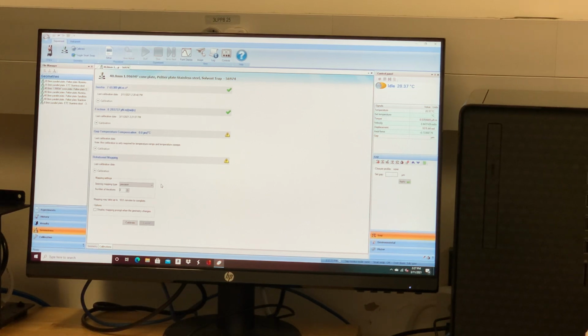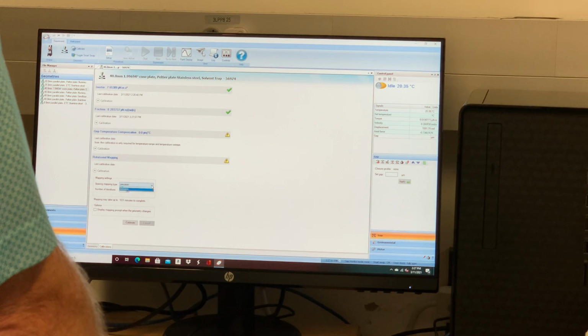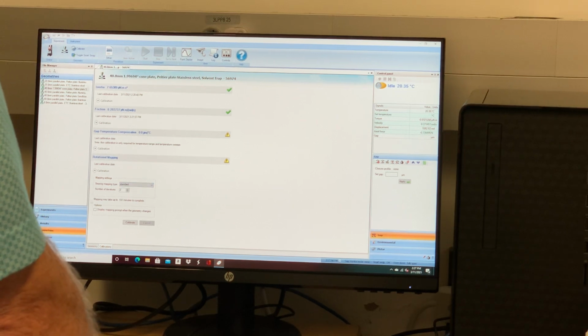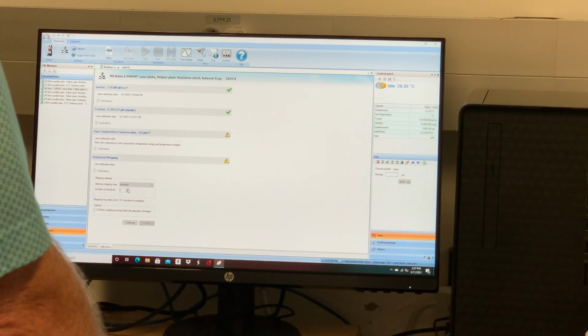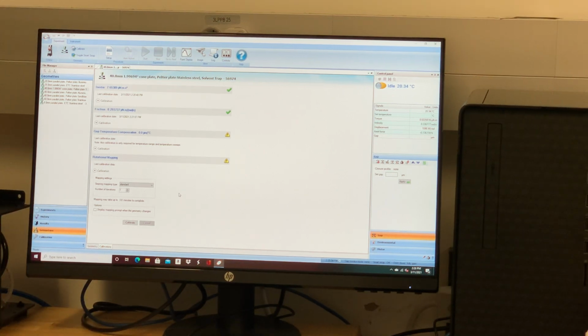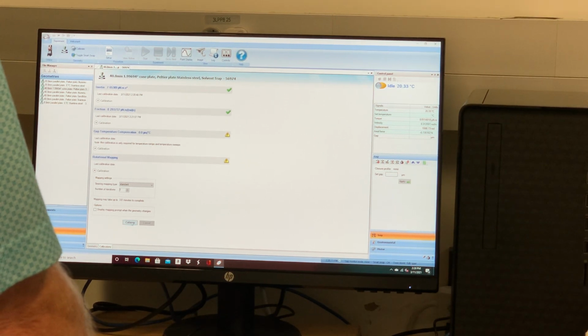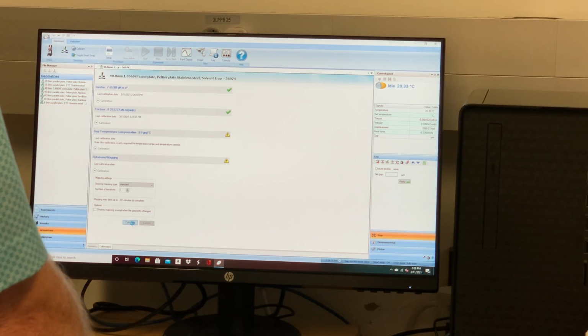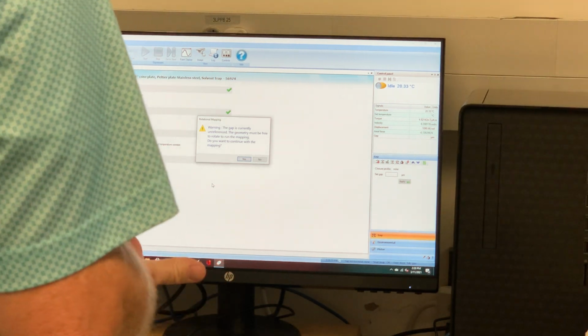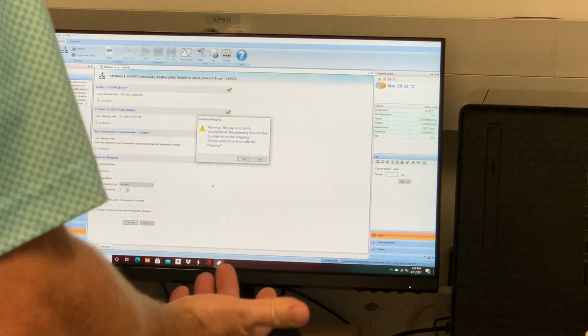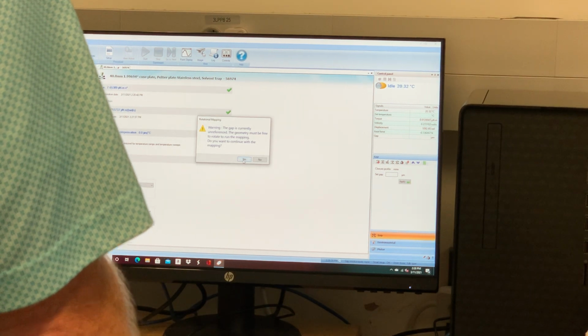So if you guys were doing low viscosity fluids, like I said, like water, it could be something you may have to do every time you run a sample. But we're going to run some S600 oil, which is 1000 CP oil, and a standard map with 1 iteration is fine for it. Okay? For oil? Yeah. So I'm going to do a standard map, 1 iteration. It's going to take 3 minutes. I'm going to hit calibrate. This message just says the gap is currently unreferenced. The geometry must be free to rotate to run the mapping. Is it free to rotate? Yes.